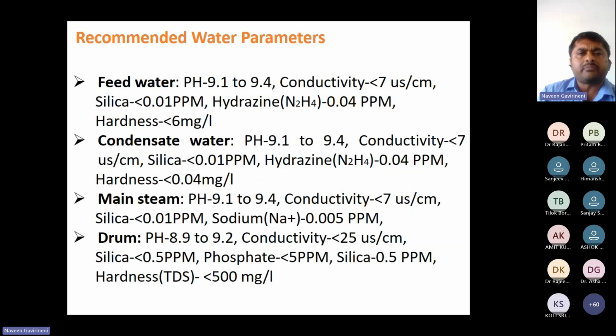So this is the recommended water parameter. Here we are considering feed water. There is a feed water arrangement. We have four types of streams: feed water, condensate, main steam, and drum. These are the parameters we should maintain. Otherwise, our steam quality is not that good for getting the power.